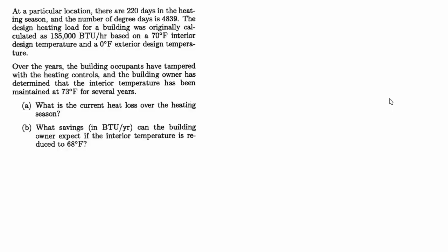101 Solved Mechanical Engineering Problems HVAC number six. At a particular location, there are 220 days in the heating season and the number of degree days is 4,839. The design heating load for a building was originally calculated as 135,000 BTUs per hour based on a 70 degree interior design temperature and a zero degree exterior design temperature.